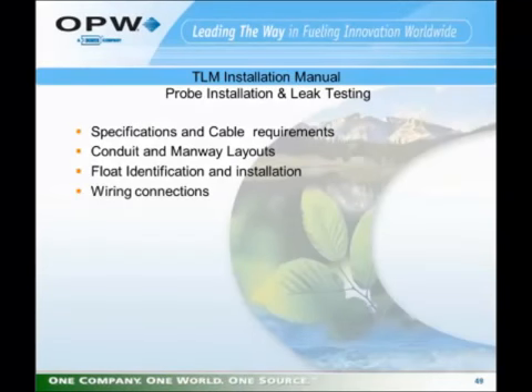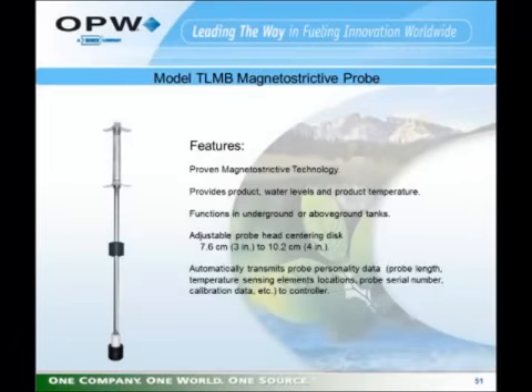The next thing we want to look at is installation requirements and practices for the EECO tank gauge family. The current probe being used on the EECO family is the model TLMB magnetostrictive probe. It's proven magnetostrictive technology. It provides product level, water level, multiple temperature readings, and functions in both above ground and underground tanks. The probe head centering disc will allow this probe to be used in probe riser pipes from 2-inch up to 4-inch in diameter. This is a digital probe that, when used with some pieces of equipment, will transmit probe personality data. This probe comes equipped with 2-inch product float and 2-inch water floats.